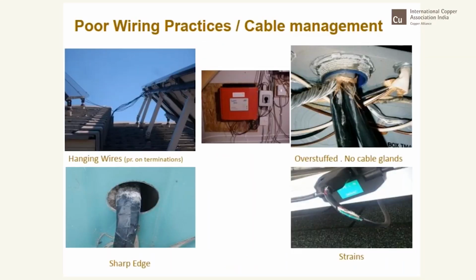And then poor wiring practice. You can see in the first one, the cable is going from one row array to another. It's just like a strand which is hanging. And when air blows, these cables will be continuously swinging from one end to another. So the connection to some terminal box can all become loose. So this can happen. And then you can see the sharp edge in the next one. The cable may be actually applying pressure on the edge of the metal container, and it could get cut, which is again a problem.